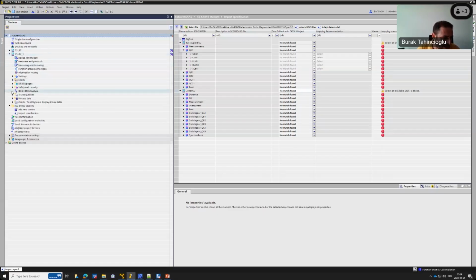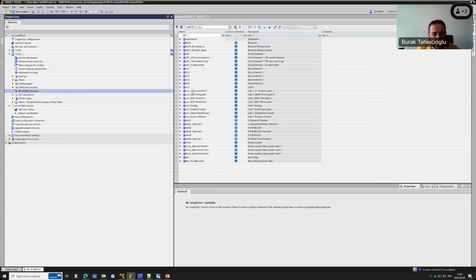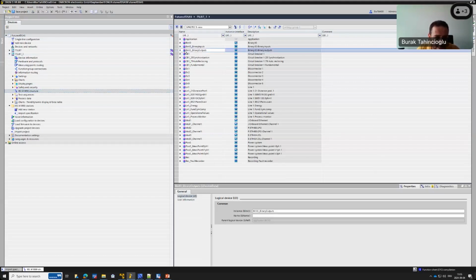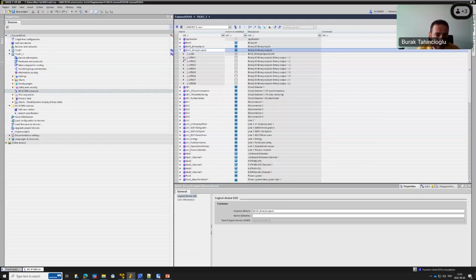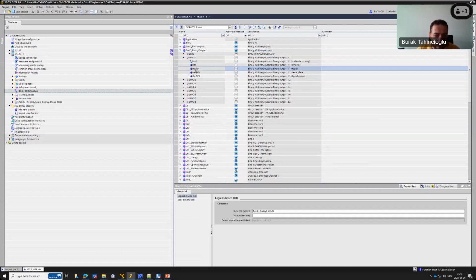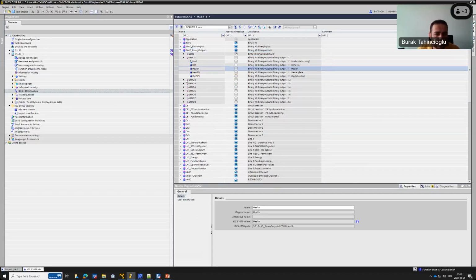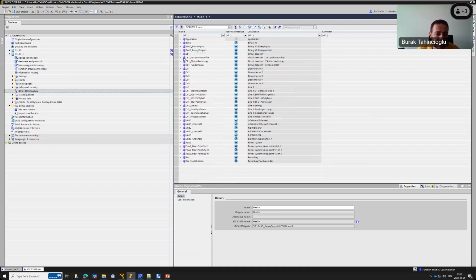You can already see they support 61850, and their structure is the default structure. The IEC 61850 structure is the data model of the Siemens IED. The Siemens IED has default logical nodes. Every function element you see is the logical device, followed by a logical node, followed by the data objects, down to the data attributes—which we don't see here, but that's not a big deal.